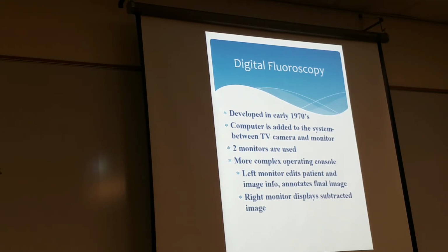Typically 2 monitors are used during digital fluoroscopy. It doesn't have to be that way with all of them, but I don't know, at your hospitals, do you have 2 monitors or 1 in your rooms? Well, 1 monitor for the doctor, then the monitor in the control room. Okay, so that's basically 2 monitors. That's all right, that's fine. You have 1 monitor for editing patient information. The right monitor tends to be a real-time image.